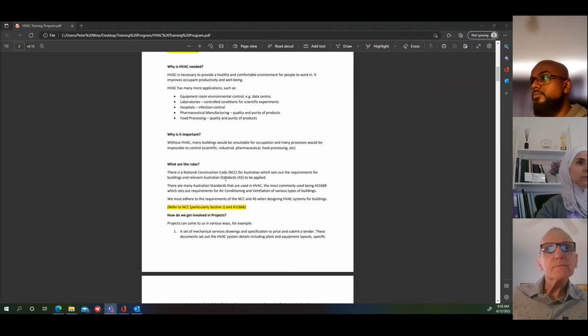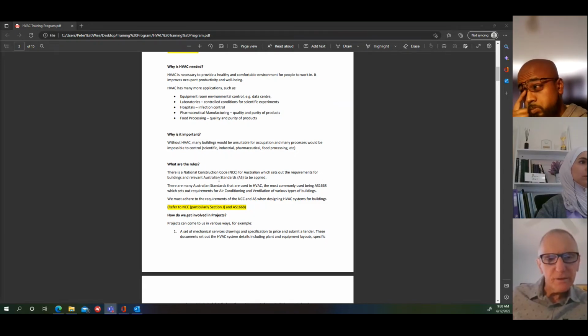In the NCC, there is a list of Australian standards, which are called gazetted standards. If they're listed in the NCC, you must comply with those standards as well. If they're not listed, but the standards exist, then they're a recommended document, but not mandatory. But you'll find always that AS 1668, Part 1 and 2, will be referenced in the BCA, so you must comply with those.